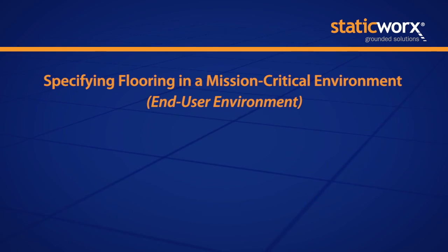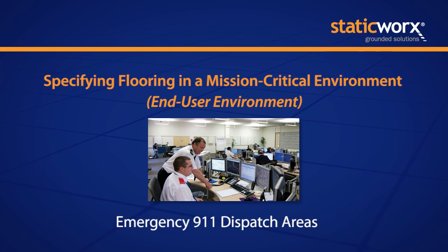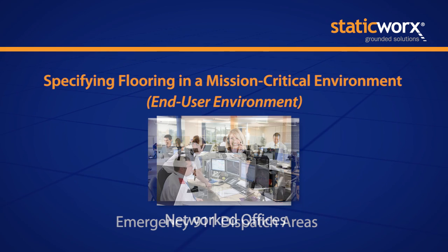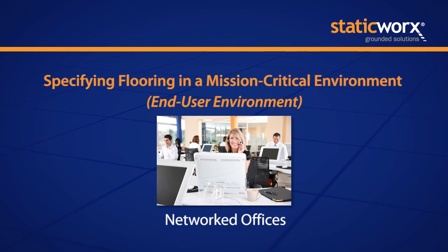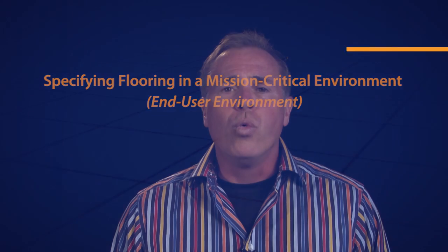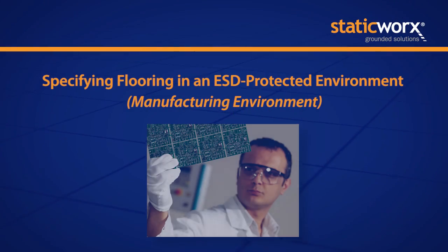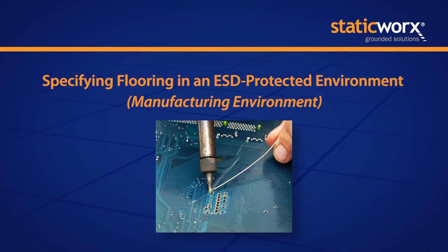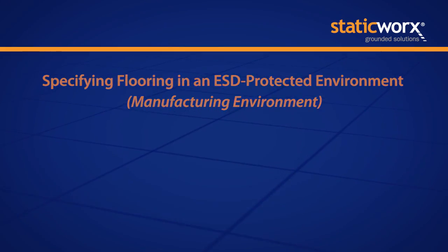If you're looking at the use of static control flooring in an end user environment, maybe it's a 911 call center, maybe it's a server room, a computer room, a data center, a war room, then you should be looking at flooring from the perspective of, will it prevent static on people wearing regular shoes? If it's an ESD-protected environment where components are handled, you're going to be looking at it as a grounding mechanism using static control shoes.